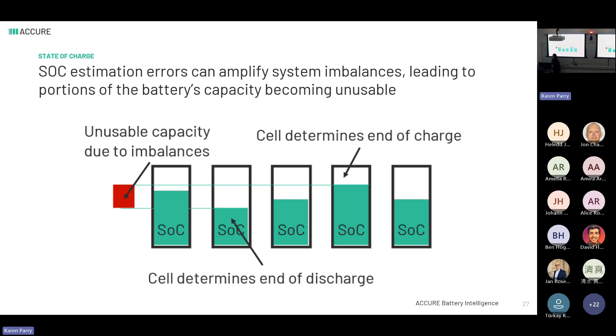That's not a normal aging rate for a battery at all, especially in year one, where likely it would have been an oversized system and it would not age that much. But if you look at it, that's how imbalances and state of charge errors reflect - they just mean you have less capacity available. But if you recalibrate the system, you can reverse that capacity loss.